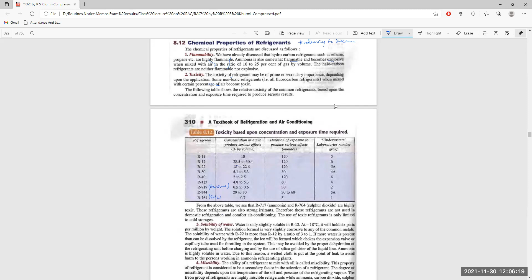Solubility of water. Water is only slightly soluble in R12, and at minus 18 degrees centigrade will hold 6 parts per million. So an extremely small amount of water is soluble in the refrigerant. The solution formed is highly corrosive to any of the common metals. It means if some water leaks inside your refrigerant system, it is extremely corrosive to the surrounding metals.